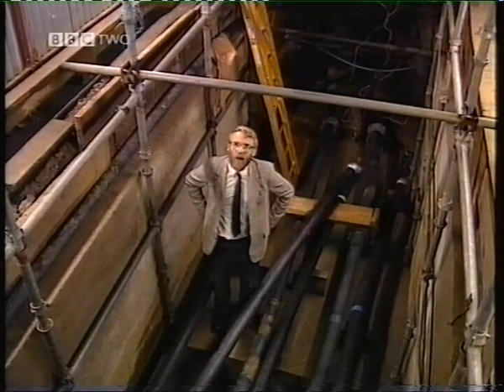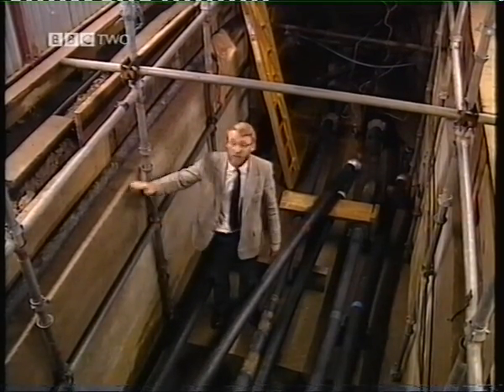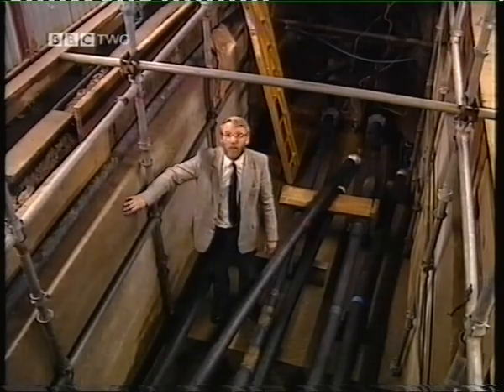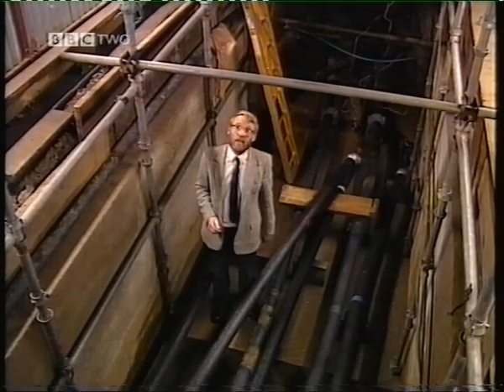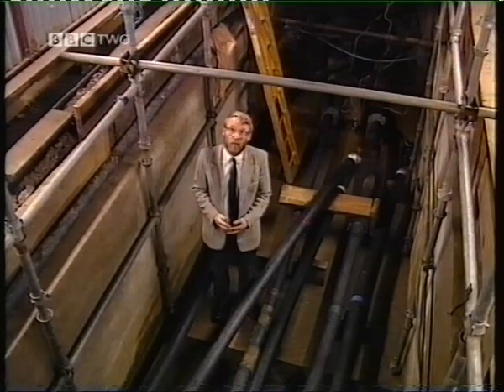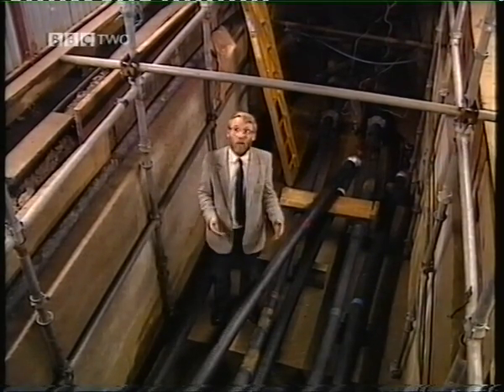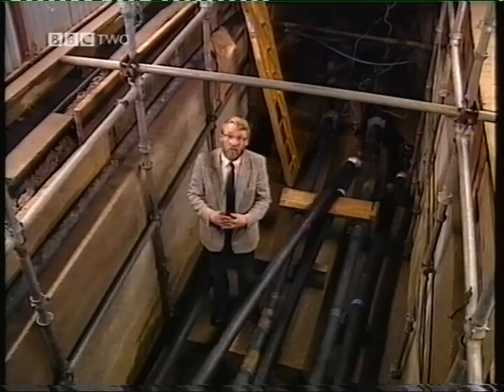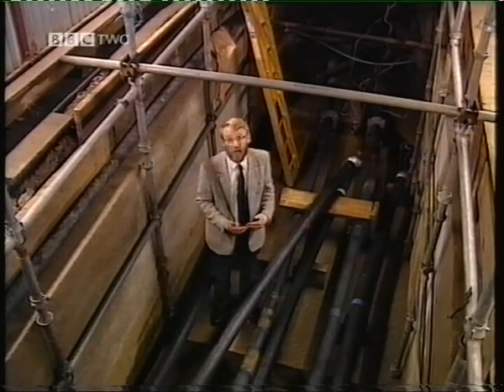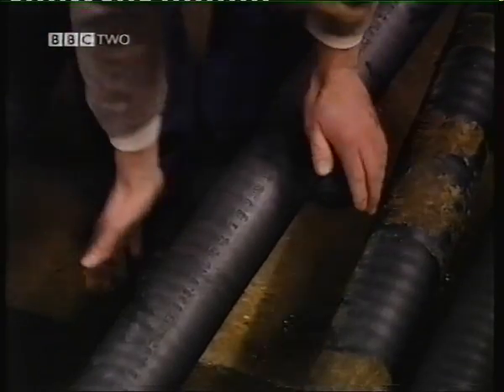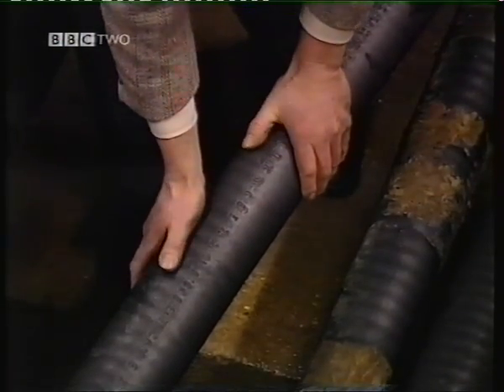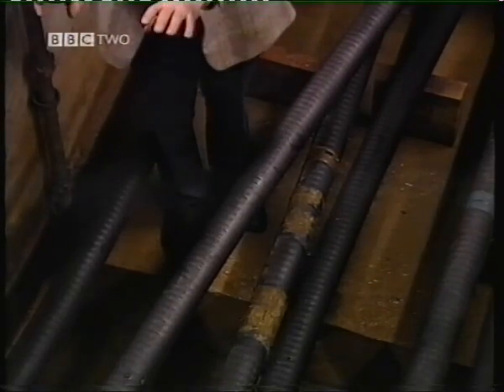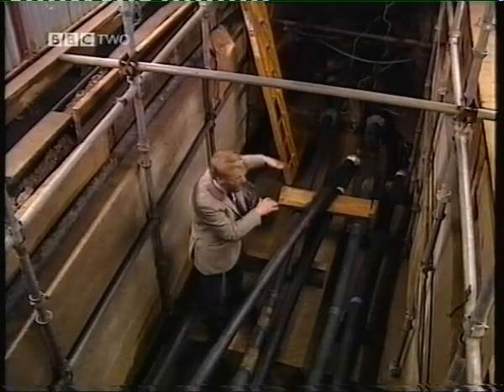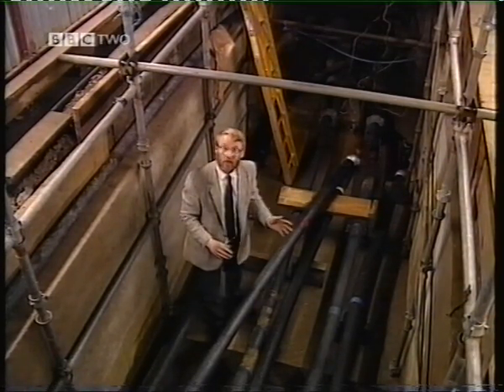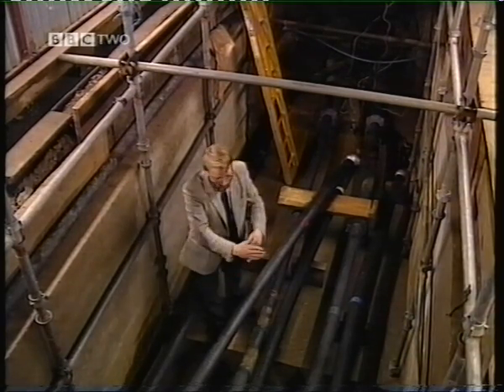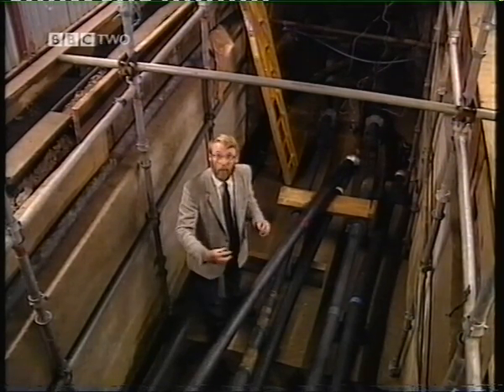This is one of the holes in the ground where the jointing is done. It's about 2 meters deep, 2 meters wide, lined with concrete. And in a couple of days' time, this is going to be turned almost into an operating theatre. They'll be cleaning it all up, and the gang will be coming in for a short period of time, about 18 hours, to start joining these cables. Here they are, 275 kV, this one, oil-filled cable, with 3 coming in that way, 3 coming in that way. We've got to keep the oil pressure on them all the time, and then they have to be cropped to length and the jointing proper.